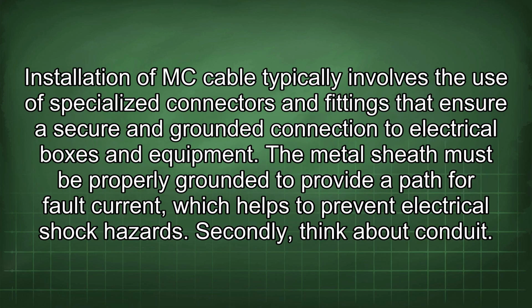Installation of MC cable typically involves the use of specialized connectors and fittings that ensure a secure and grounded connection to electrical boxes and equipment. The metal sheath must be properly grounded to provide a path for fault current, which helps to prevent electrical shock hazards. Secondly, think about conduit.